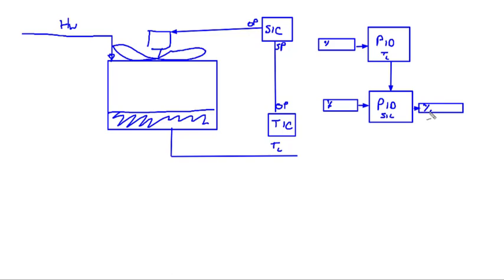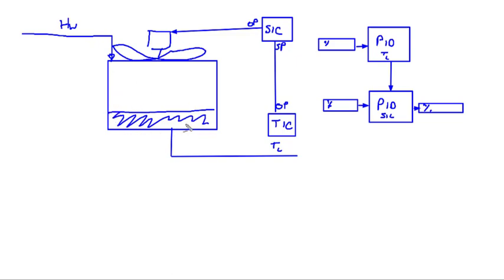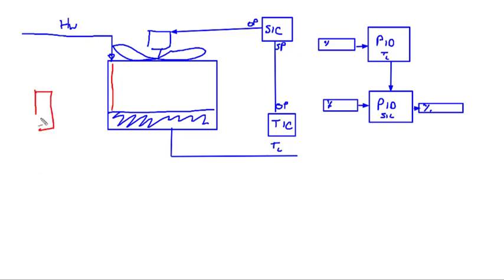The first problem we had is the plant people said this never worked, I could never tune this temperature loop. Now one has to look at this very carefully. If I was going to draw this particular section of the process, what is coming in is not mixed, so you could almost visualize this as a plug flow reactor, not quite. Your temperature profile is going to change over the length.